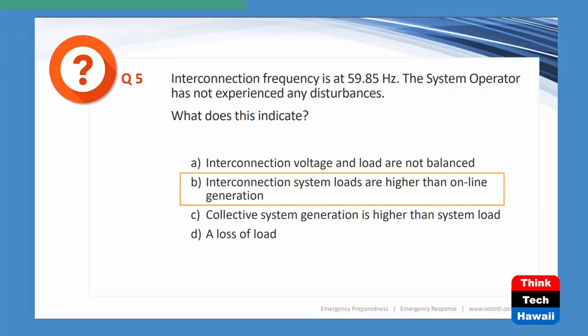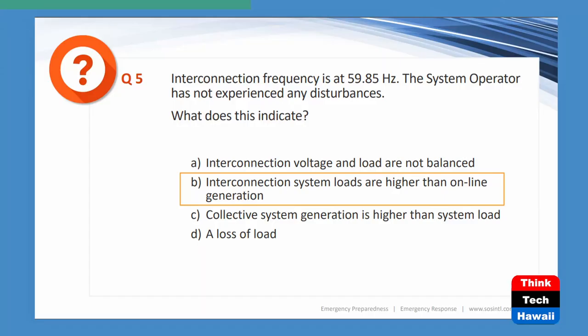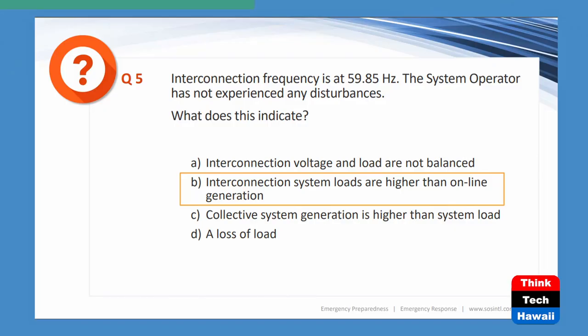C, a collective system generation is higher than system load. That is the exact opposite of what's happening here. If that were the case, you'd have higher frequency than 60 hertz. So in this case, C is not the answer. And then D, a loss of load. Again, not the answer either, because if you lost load, you'd have more generation than load, and you would have higher frequency. So in this case, Bravo, interconnection system loads are higher than online generation, is the correct answer. So of course, that means that you don't have enough generation to supply the load.